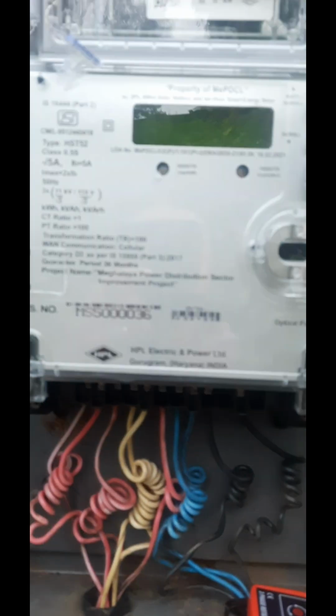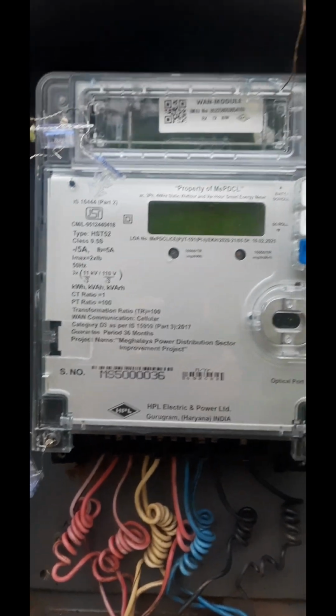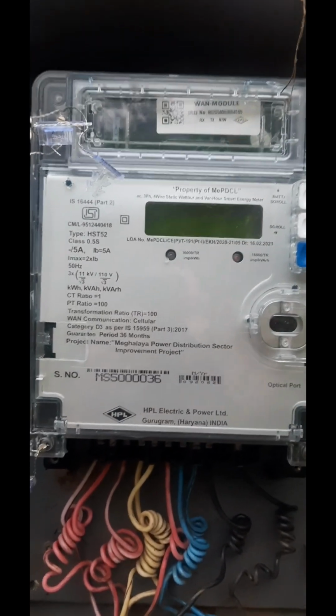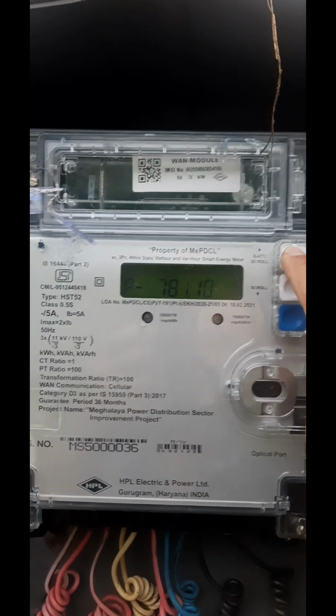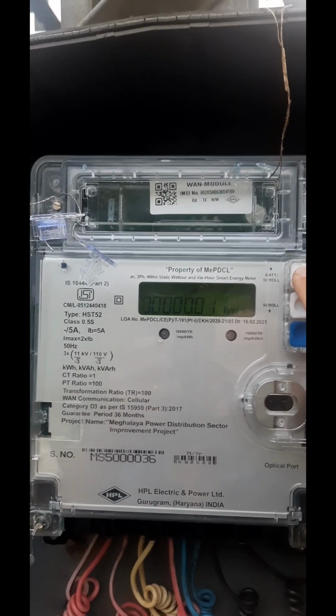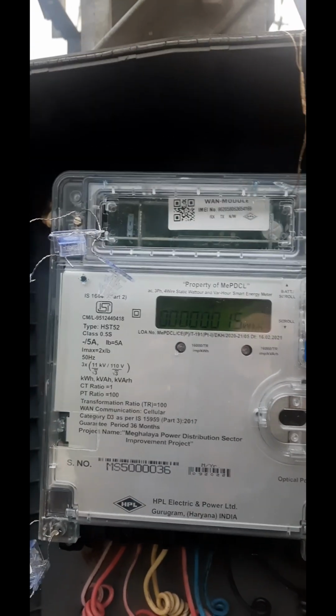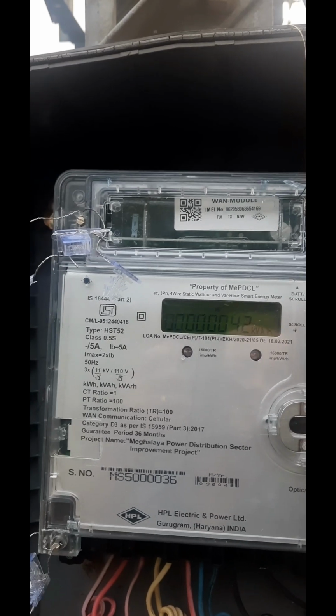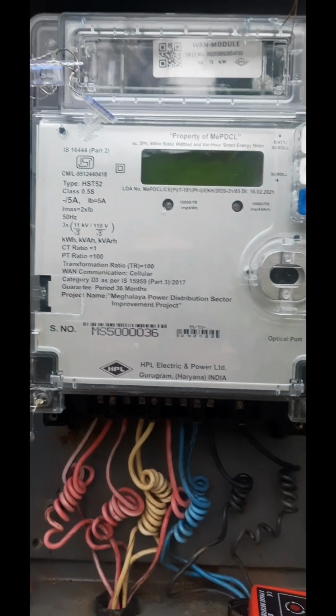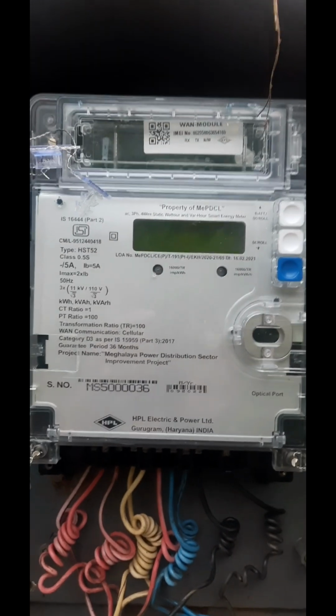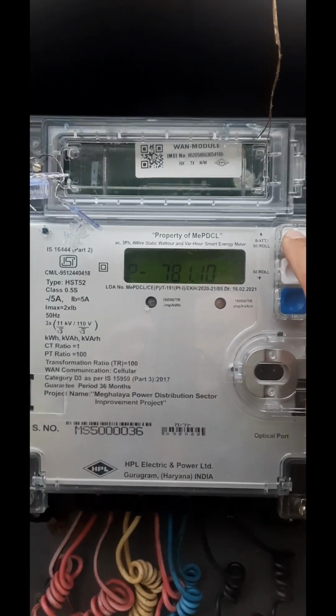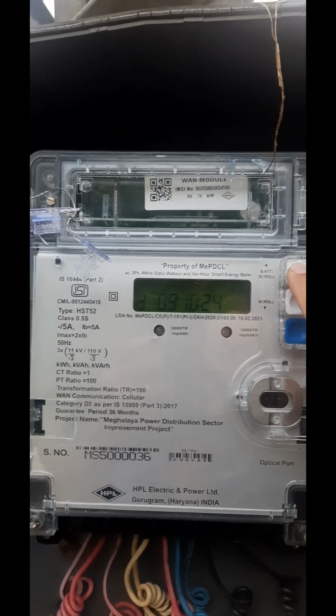And then the meter ratio, we have to see the internal PT CT ratio of the meter. The internal CT ratio is 1. That means if 1 ampere enters the meter, the current will show 1 ampere, and the PT ratio is 100. That means if 1 volt enters the meter, the voltage shown by the meter will be 100 volt.